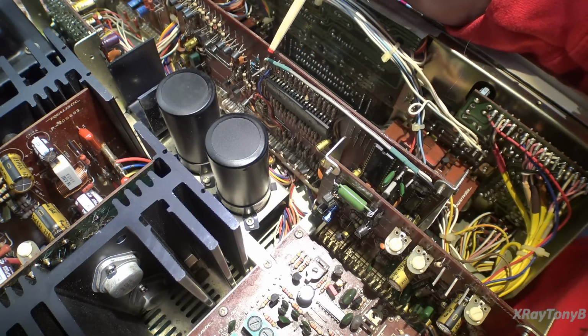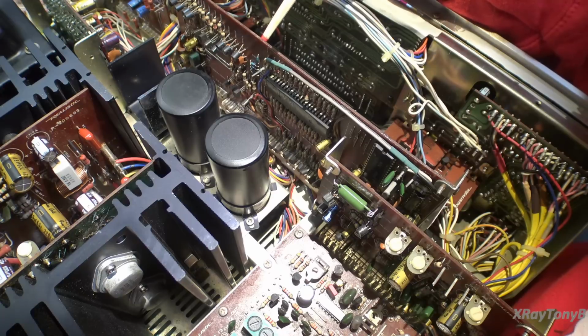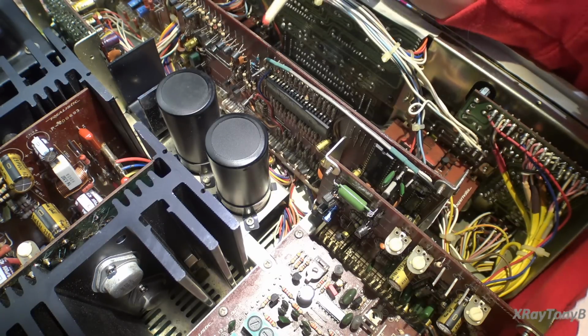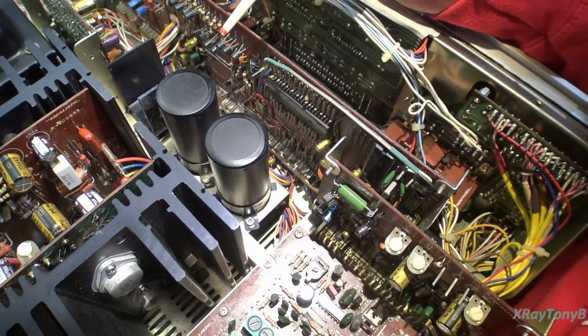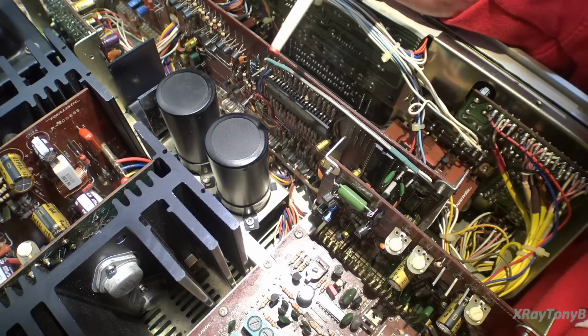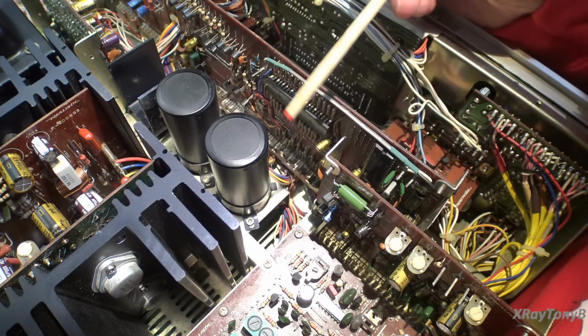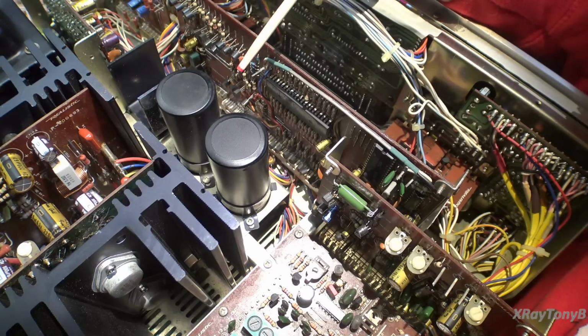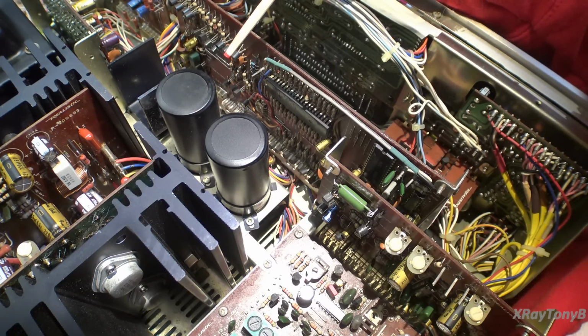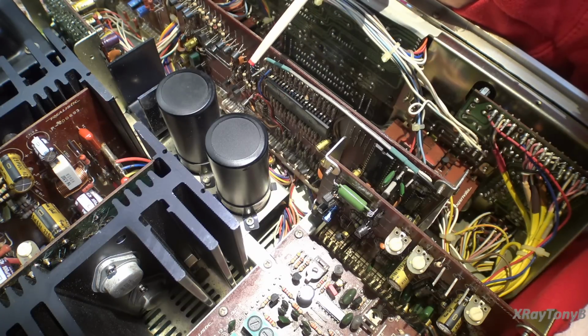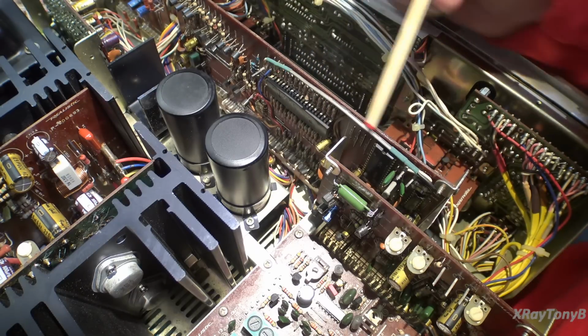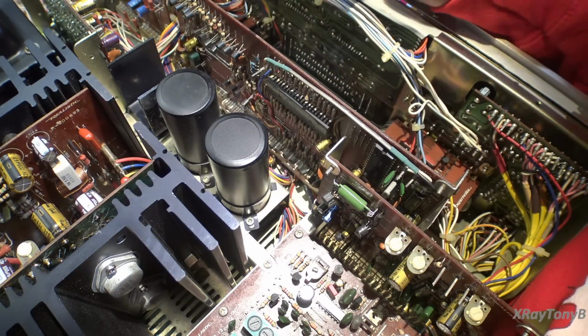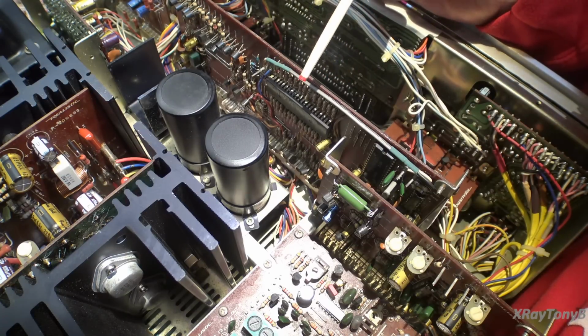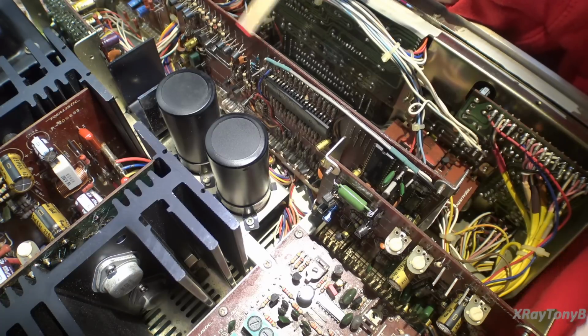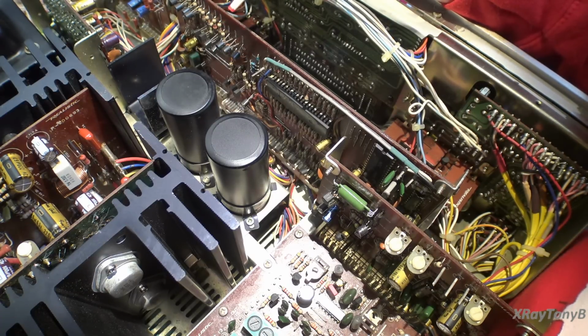So one of the things it does is it has to have a very accurate clock in order to operate, and that clock just so happens to be 160 kilohertz. And how did they derive that number? Well, if you take the 10.24 megahertz of the reference oscillator, what it's supposed to be, and you divide that by the 160 kilohertz, you'll find that the number is 64. So your PLL chip actually has a divide by 64 output on it, and that is how we're getting it.